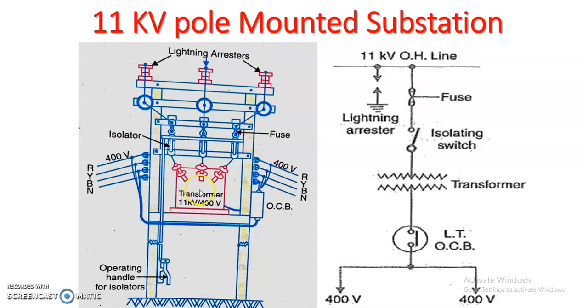Then that step down transformer steps down the voltage to 400 volt, 3 phase 4 wire system, as this transformer is delta star. That means the primary winding of this transformer is delta connected and the secondary winding is star connected. Then the 400 volt supply is given to the distributor line. Here we can connect R, Y, B, N. These are the distributors.